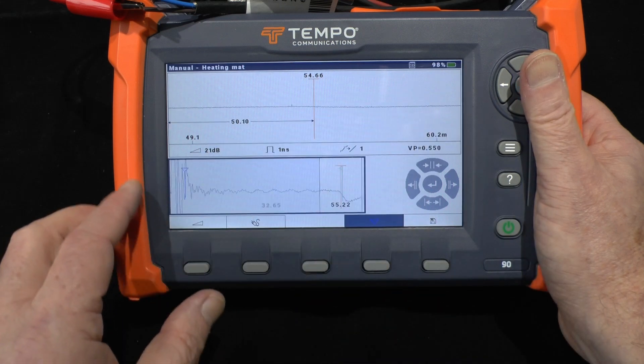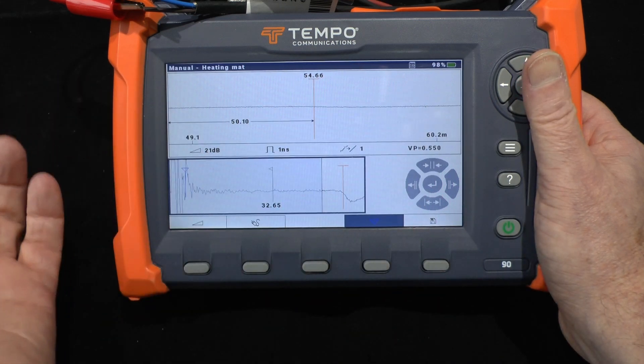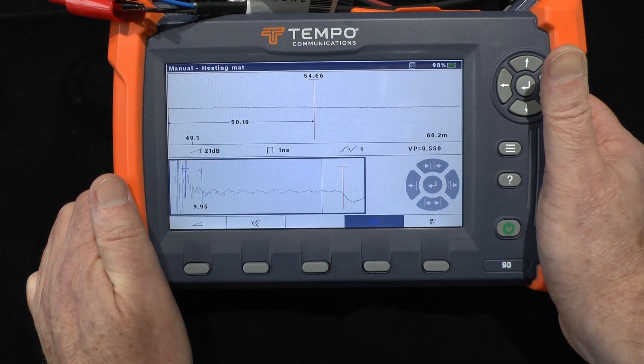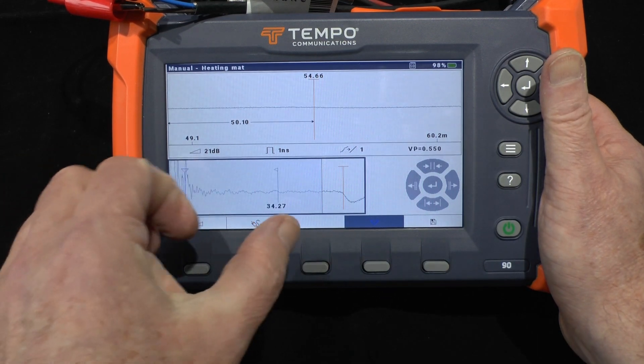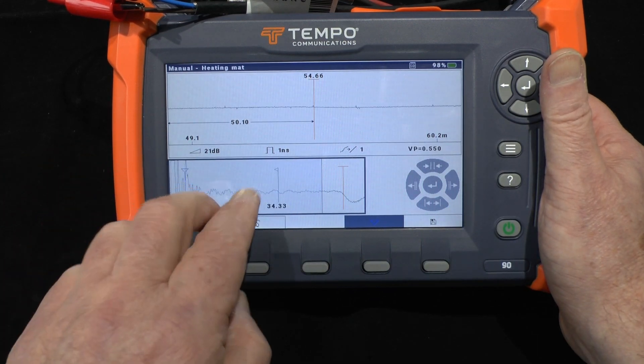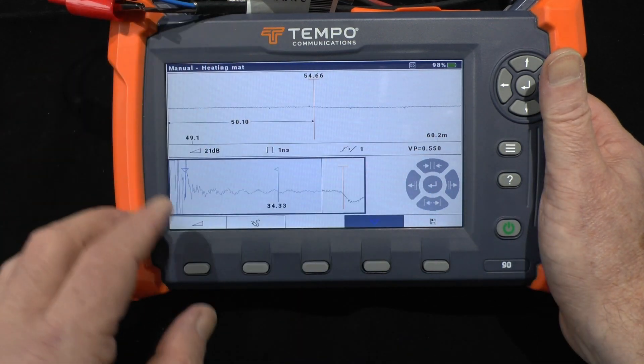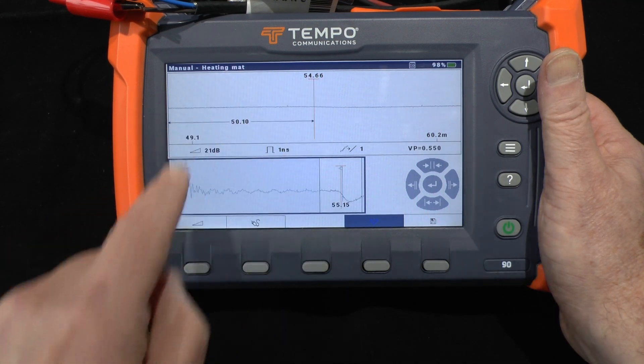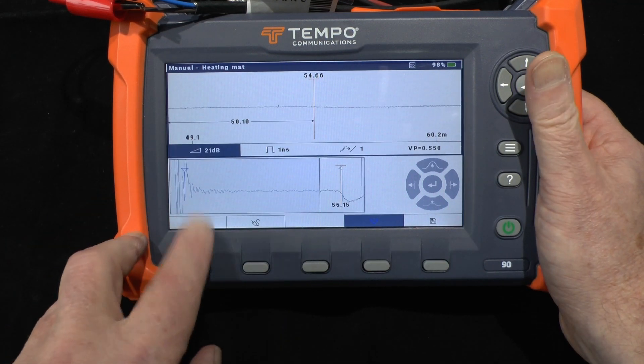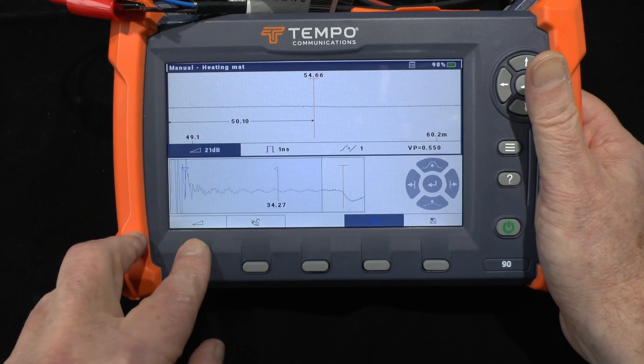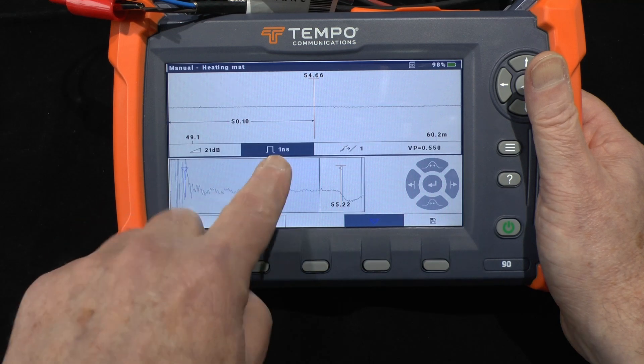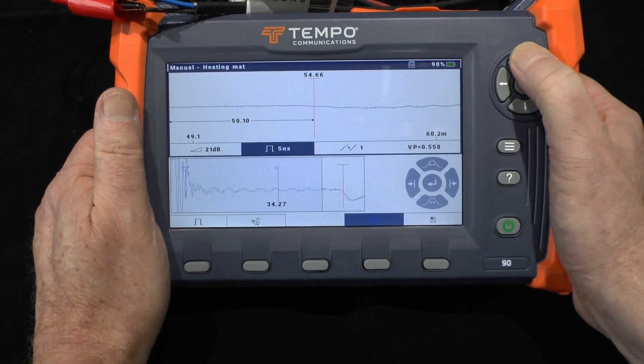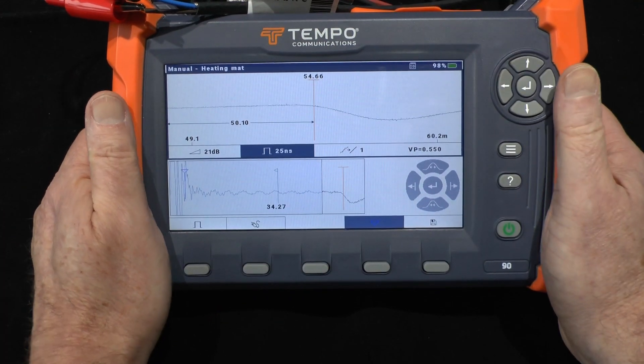There is a very slight dip here, and because heating cable is by nature resistive and lossy, the pulse that's gone in is being stretched out and expanded. So I'll go into the upper trace by pressing the parameters button, navigate to the pulse setting, and increase it to 25 nanoseconds.